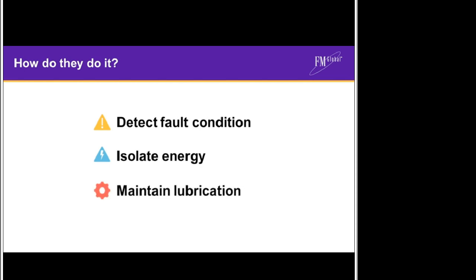The final action steam turbine safety devices need to complete is to maintain lubrication until the machine has run down. Lubrication failures don't often produce the spectacular visuals shown in the previous slides with turbines leaving the building, but they occur with alarming regularity and often lead to serious damage. As a company, FM Global averages approximately £100 million a year in gross steam turbine losses around the world. Loss of lubrication events consistently make up around 50% of that figure.